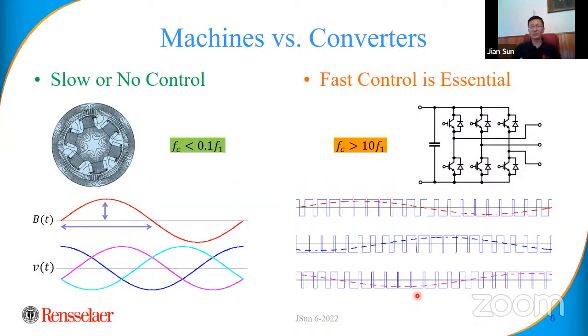So if you look at the generator machine level, there are really two fundamental control functions: one is to regulate the excitation field so you can control the voltage, and the other is to control the speed of the prime mover so that you can regulate the frequency. So these are two basic control functions: voltage control and frequency control. Each corresponds to a physical quantity you regulate—voltage control is the magnetic field, it's current control, and frequency control is the mechanical time constant, the rotating speed.